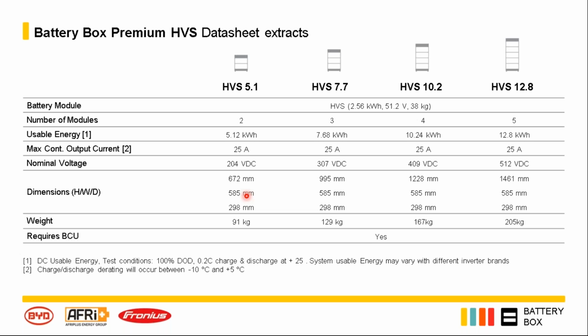In terms of how this affects installations, these voltages are very similar to your solar voltages, and your currents are also fairly low, handled by 6 square wires. So practically, installing these batteries is very similar to your solar panel installations, similar in voltage and current. The big difference is the short circuit - you can short circuit your solar panels and get your short circuit current, but it's best not to short circuit the batteries.